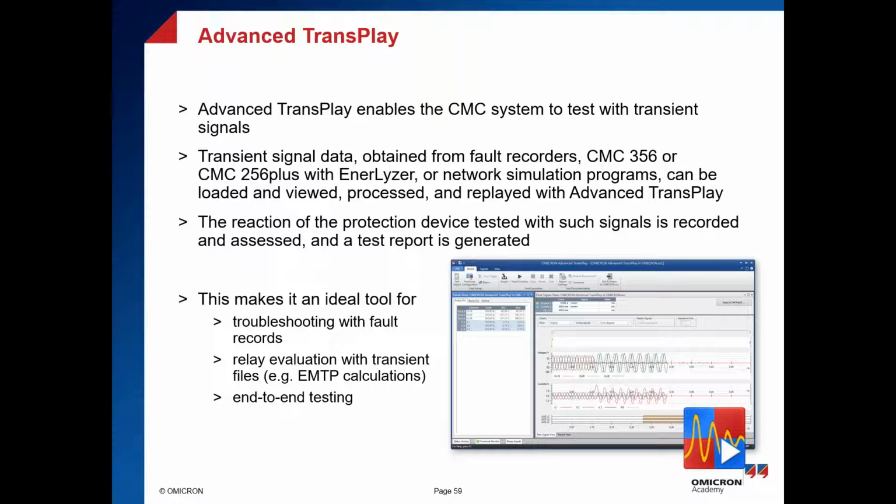It's also useful for people who study the system by using other software like EMTP, MATLAB, or any software which is able to export the COMTRADE file, and you can play it back on a protection device. It can be used also for end-to-end test. We will see this together because we are able to use time trigger condition.